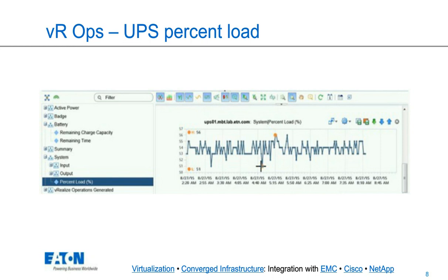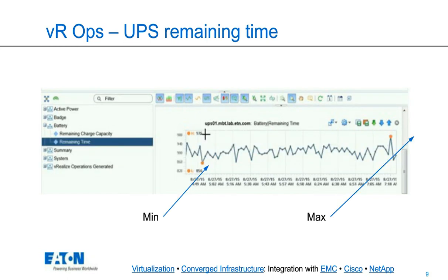And the third screenshot here shows remaining runtime. Now, this is probably not typical. We're looking at a 900-minute runtime. That's 15 hours. But anyway, just to show the point, you're polling continually, and you're graphing these numbers all the way through time. Again, it was August 27th, the morning hours, and we did log a low of 856 minutes of runtime remaining, and we logged a high of 975.